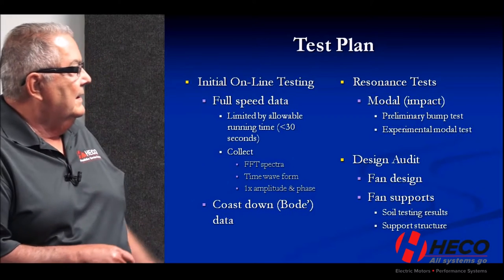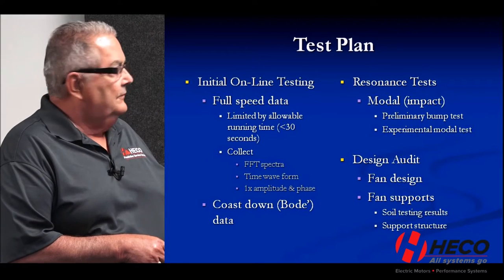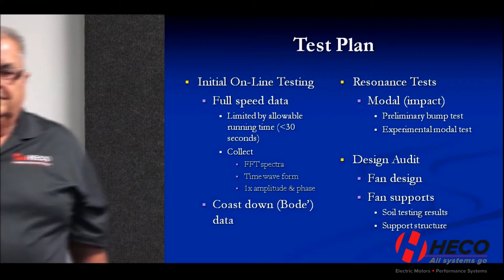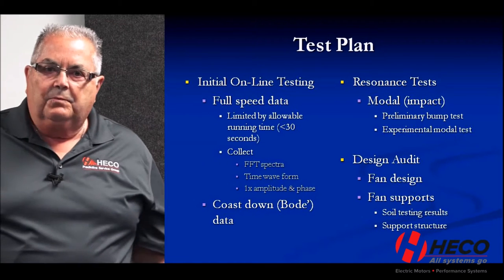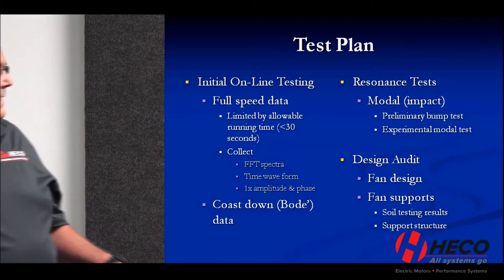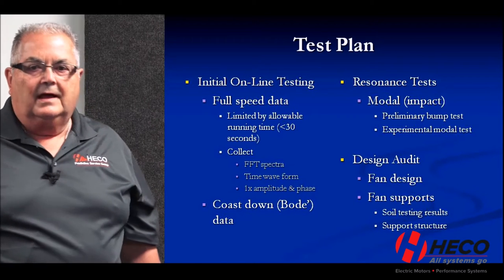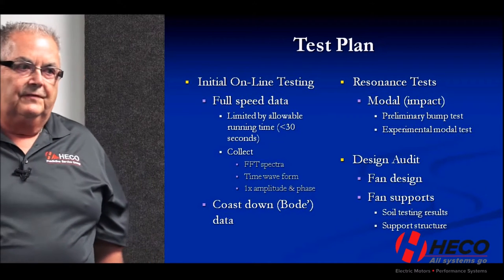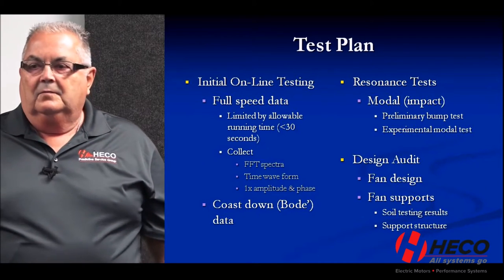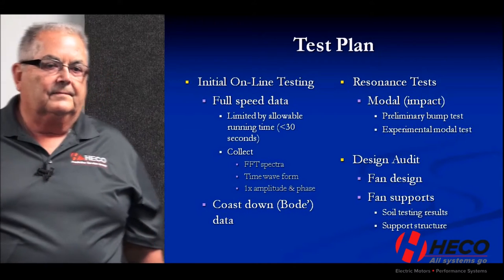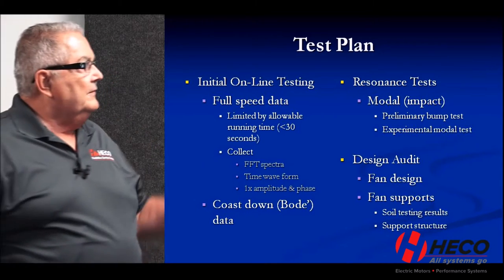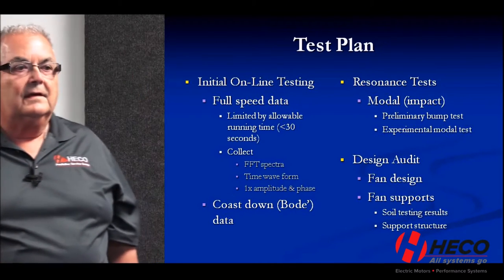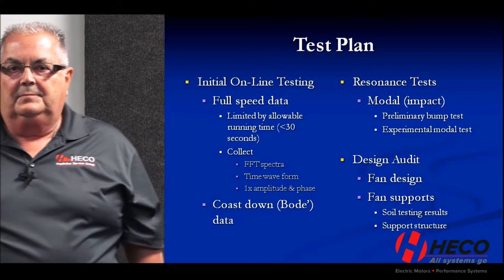I wanted to collect FFT spectra, time waveform, and 1x amplitude and phase. The best we could do was probably get one or two points and then be set up to get a coast-down Bode plot, so we could see the vibration when he trips the fan after 30 seconds and capture the coast-down. For offline testing we could also do some resonance testing techniques that don't require the fan to be running.